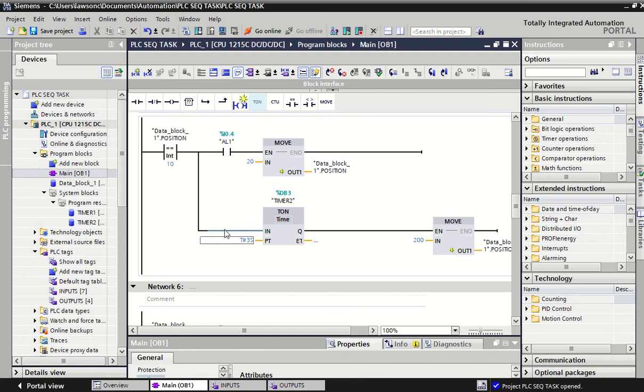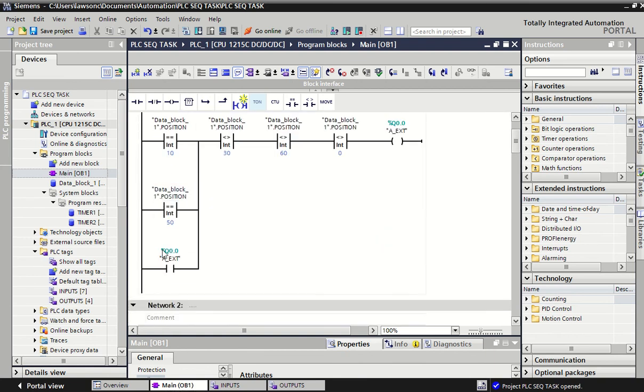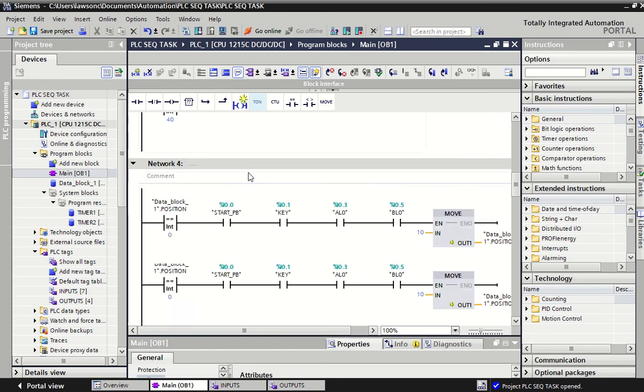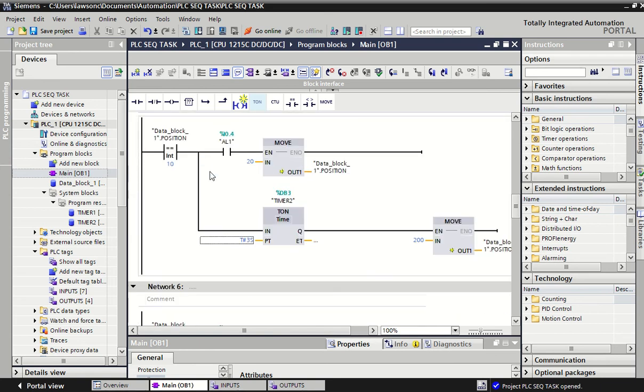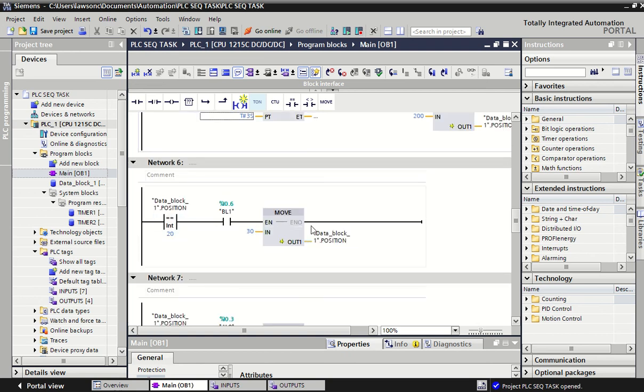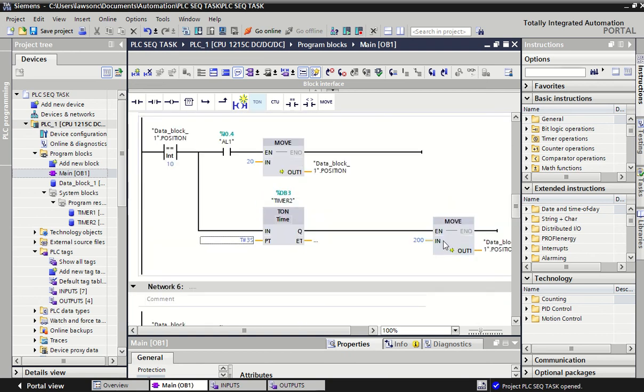And this is our decision tree. It happens on this side. It's not so much branching and latching, which is happening on the left. We're branching out towards the right. So we're giving it two options: in step 10, depending on some condition, depending on the speed of the system, the speed of the cylinder, it will either go to step 20, which means it just continues on from here, or it'll go to step 200. So I'm hoping that makes sense, and that's really where the main complexity comes into it.